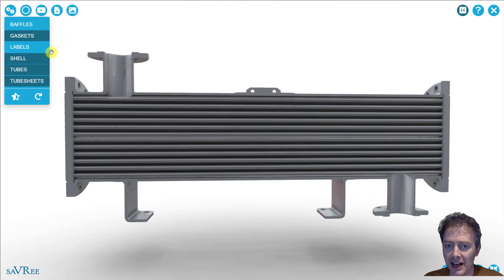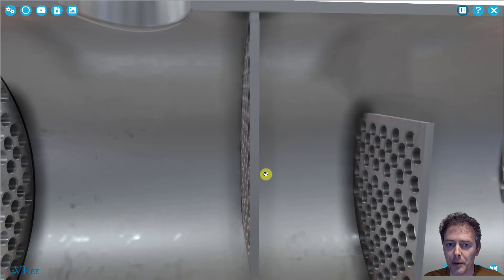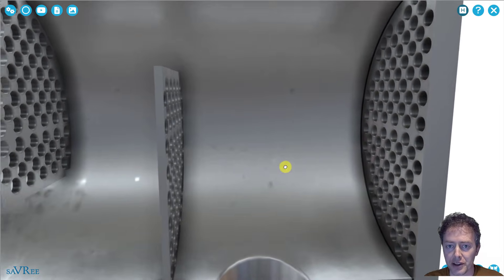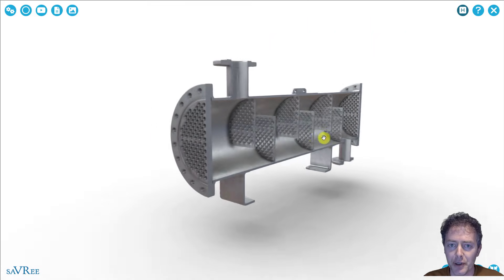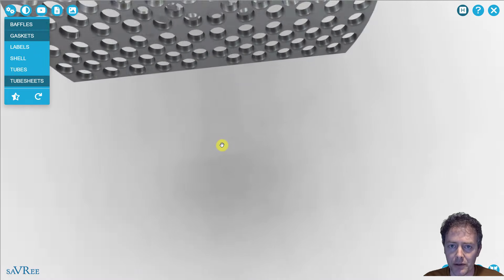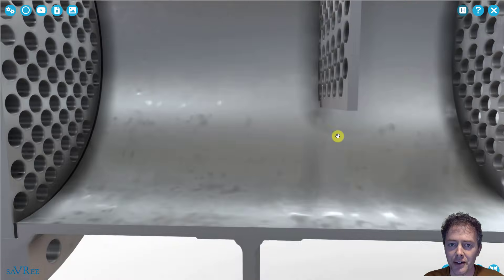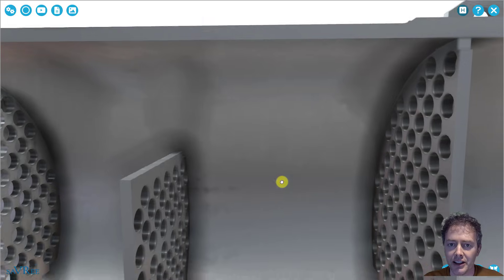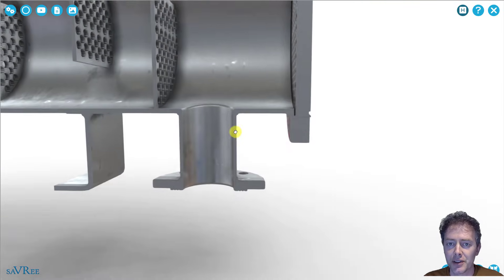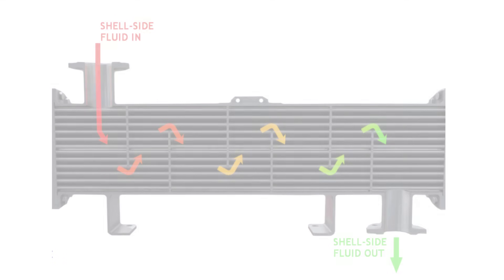The only other part we need to discuss now is the baffles. The baffles have an alternating pattern — installed one up, one down, one up, one down — and then the shell side fluid flows out through the exit connection. The reason we do this is because the shell side fluid comes in and flows downwards. Due to the baffles, it flows down to the bottom of the shell, then under the baffle, up, across, down, and continues flowing until it leaves the heat exchanger. By installing the baffles, we are directing the shell side fluid to flow over the tubes many times.